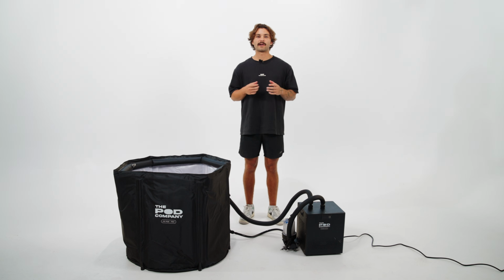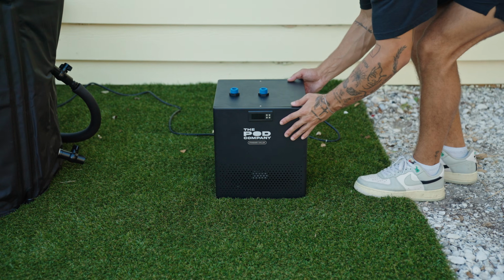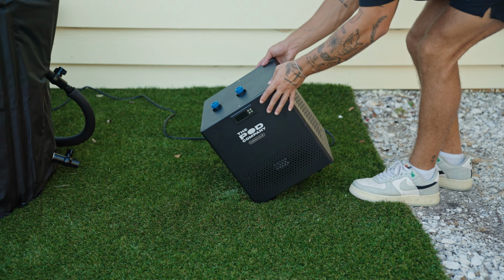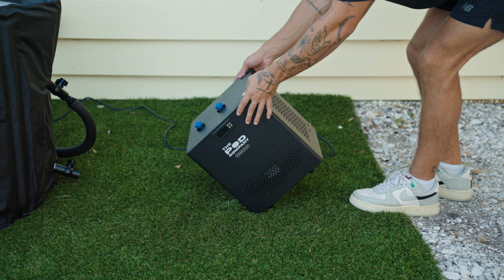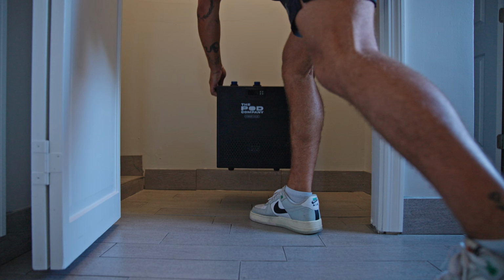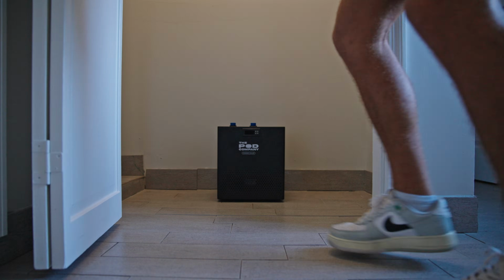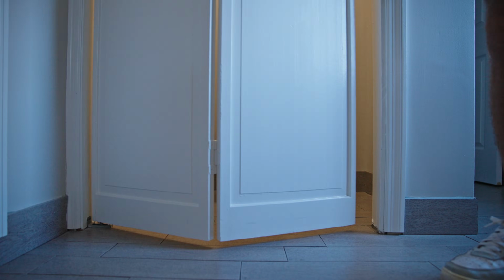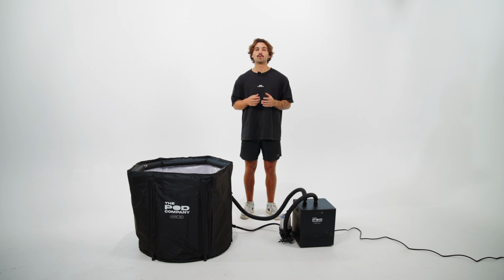To prepare your chiller for storage, start by draining all water from the IcePod, hoses, and chiller. Tilt the chiller slightly to one side to remove any remaining water. Once everything is dry, store your chiller and accessories in a cool, dry place. Now this is important. The chiller is designed to cool water and can't heat water up, so it should not be used if temperatures drop below 32 degrees Fahrenheit, as internal components could freeze and break.